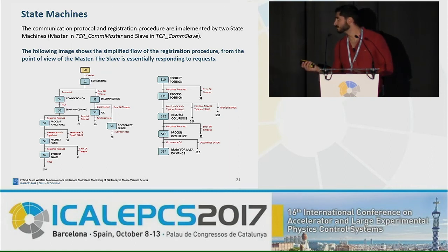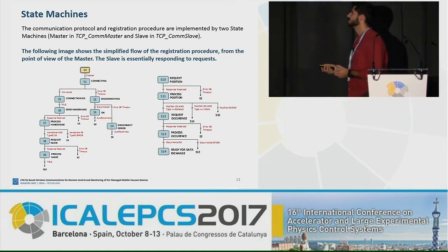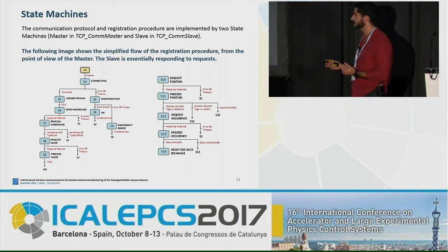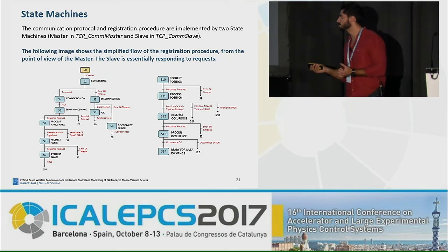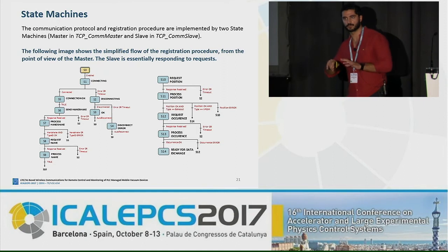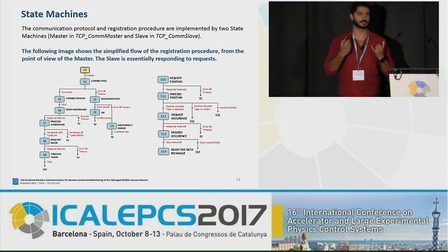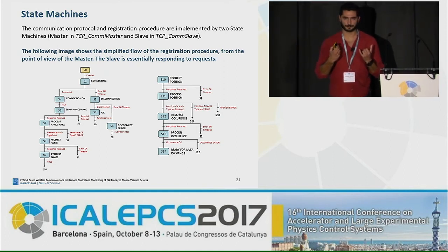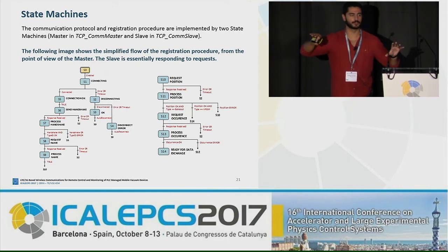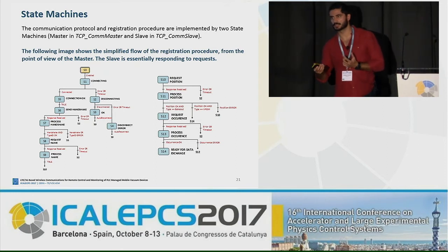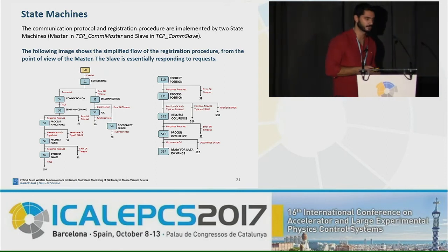So whenever the master checks that the communication is up, it sends a handshake to one of the mobile devices, and the mobile device responds with the correct handshake. And then this whole procedure of requesting the name, the position, and the occurrence happens. Once everything is done, if everything worked correctly, the device now appears registered on the SCADA, exactly in the synoptic where it should appear, and the cyclic data exchange commences. So the master continuously requests the state and sends commands to each one of the devices.